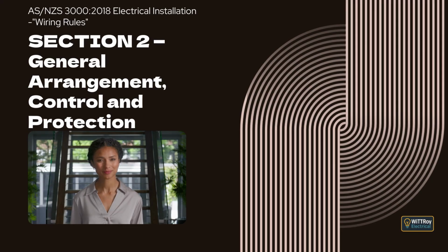If a final subcircuit shares a neutral, the actives and the neutral must be controlled together using linked devices. The neutral must be clearly marked at the switchboard so people know exactly which actives it belongs to. If an appliance can be supplied from more than one source, all those supplies must have one common isolating switch. This prevents confusion and makes sure the entire appliance can be made safe during work.